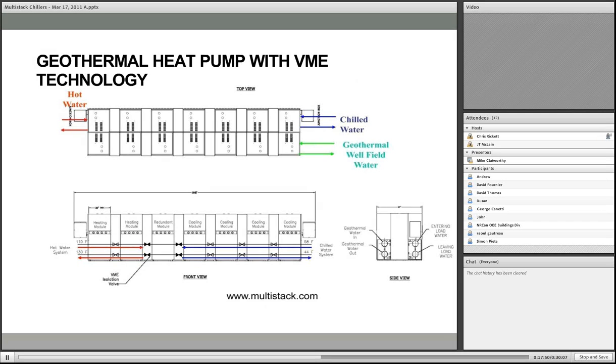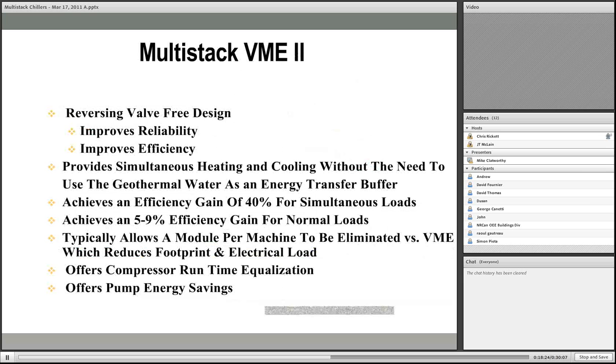On the front of the diagram, we'd have a hot water connection here, chilled water connections here, and on the back of the chiller, the common source sink, and in this case, a geothermal well field. And by closing the right set of valves, we can put 2 modules in heating and 4 modules in cooling. And this would be a classic 4-pipe system operating on a common source sink. And in this case, 1 module is not being used. But the beauty of it is we can take 1 module and make it do heating and have all the rest in cooling. So it's a beautiful way to do simultaneous variable heating and cooling. And this was what we call VME1, but we're moving on to something called VME2.